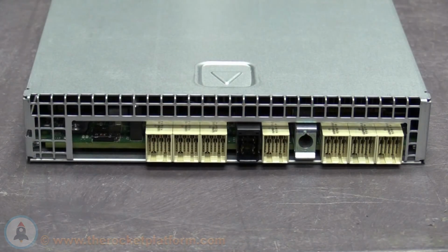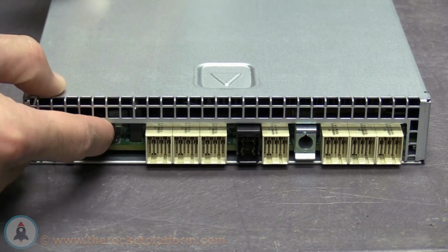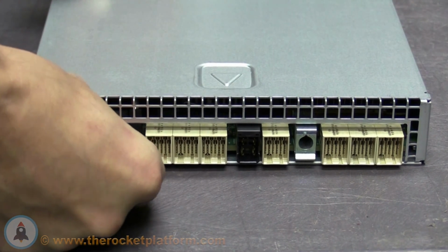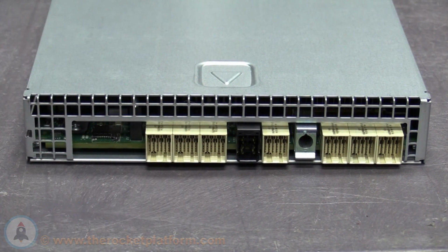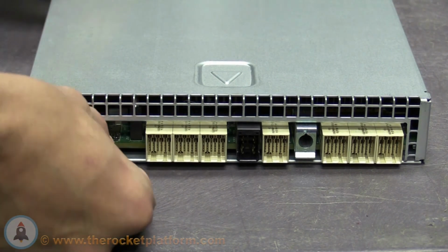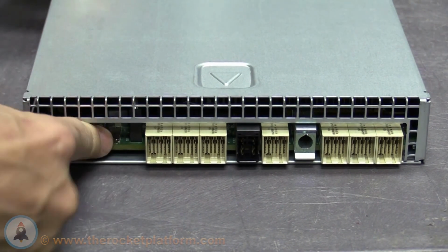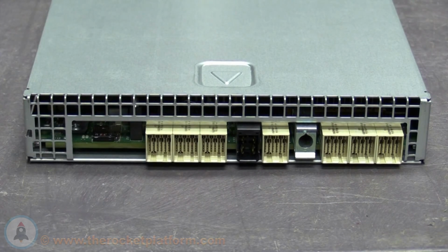You must now move the SD card from the faulty controller to the replacement controller. In the rear of the controller, you will see the SD slot. Push in on the SD card, releasing it from the slot. Pinch on it and pull back until it is fully removed. On the rear of the replacement controller, insert the SD card until you hear a clicking sound. Once the card clicks in place, you are now safe to insert the replacement controller.